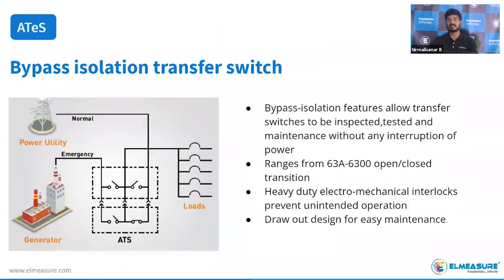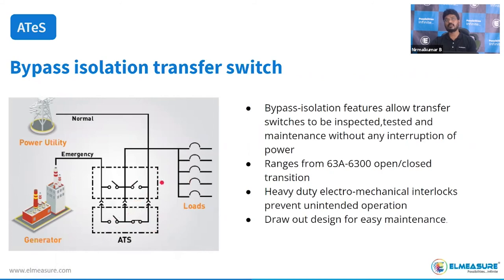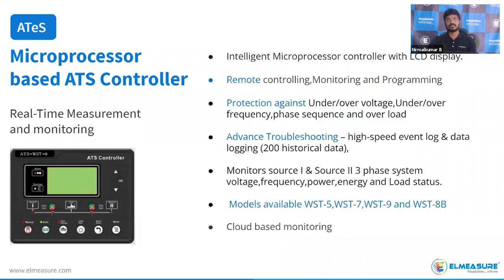For bypass isolation: two ATS units are integrated — a primary ATS and a secondary ATS. The load is normally connected through the primary ATS. If any breakdown occurs on the primary ATS, we can bypass the load to the secondary ATS. For ultra-critical applications like airports and data centers, ATS with bypass isolation is recommended. The bypass ATS features a draw-type ACB design for easy removal, repair, and reinstallation. Minimum range is from 16A to 6300A, available in open and close transition, heavy-duty electromechanical design.